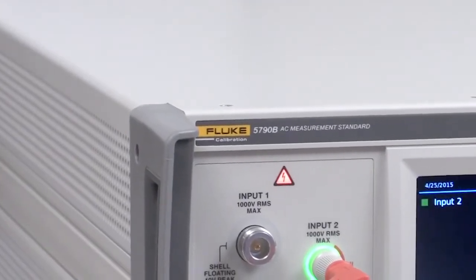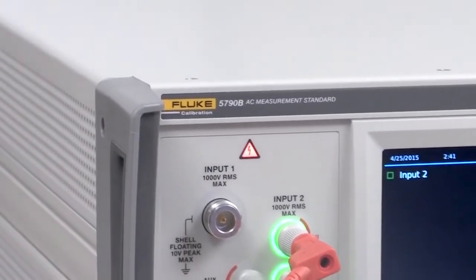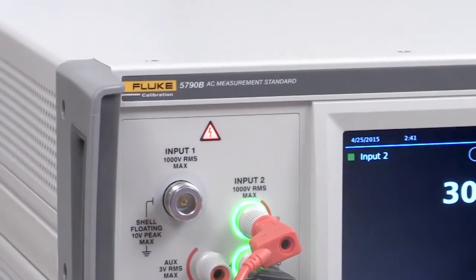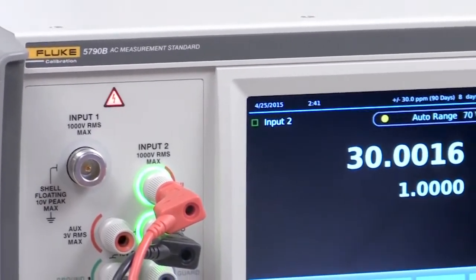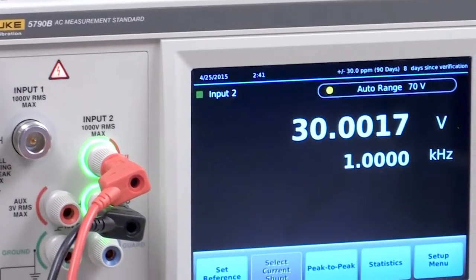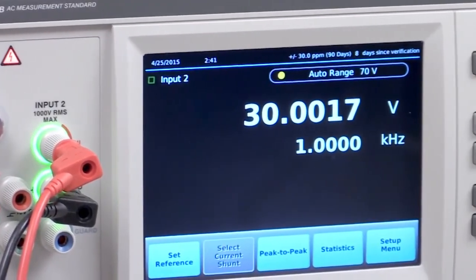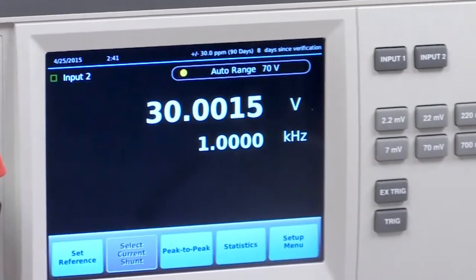The 5790B AC measurement standard is an AC measurement and transfer standard that lets you make AC voltage and current measurements with accuracies as good as 24 parts per million. It combines the accuracy you would expect from a thermal transfer standard with the ease of use of a digital multimeter.